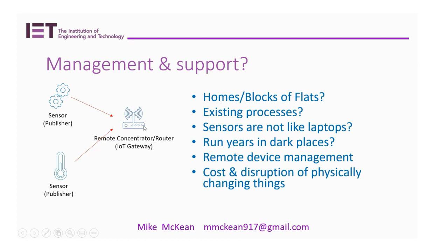these gateway type devices will usually not have an on-off switch, no power switch. They'll run years, 17 years. I've had something run 17 years in a dark place. No fans, no moving parts, and designed to run from maybe minus 40 degrees to plus 70 degrees ish, or minus 20 to plus 40. So it depends on your environment, but they will run for years in a dark place.